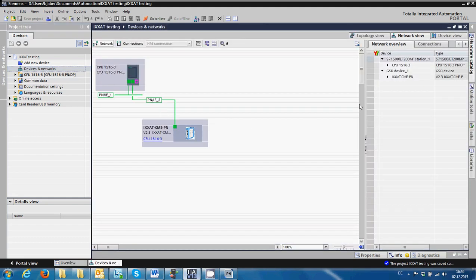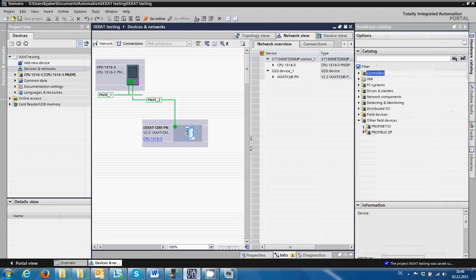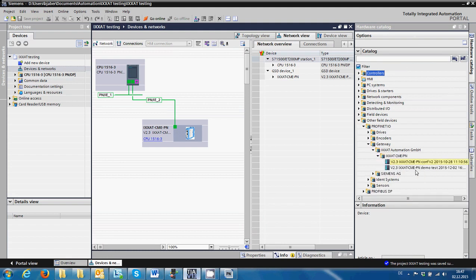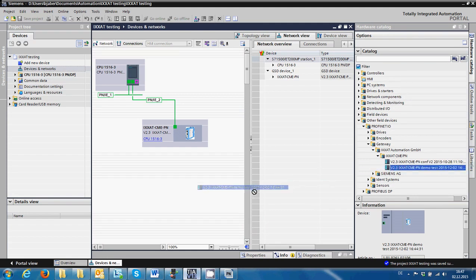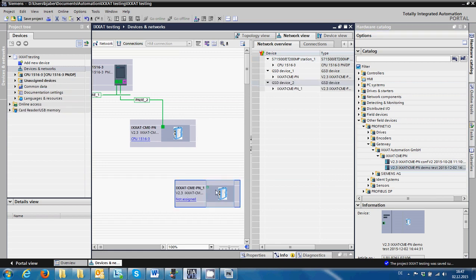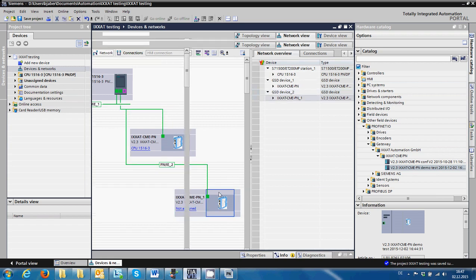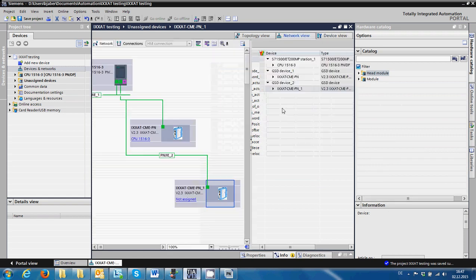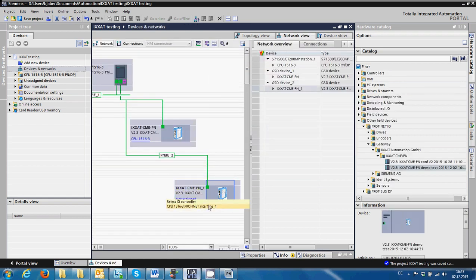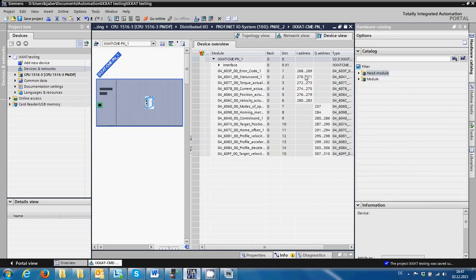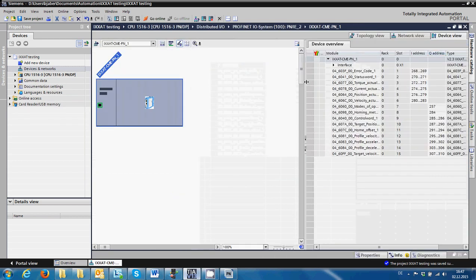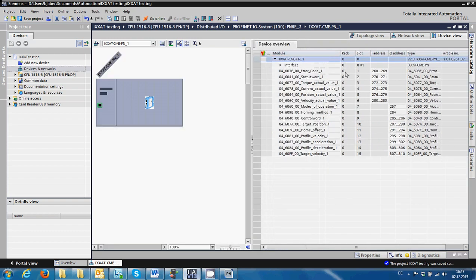Now I will go to Devices & networks. Let's open the catalog and insert a new device — the IXXAT-CME-PN gateway. This is the old configuration; this is the new configuration, as you can see it has today's date and time. Now I will drag it and put it here, connect it to the Profinet network, double-click on it, and assign a CPU. You will see it has automatically all the parameters that we configured before in the software.